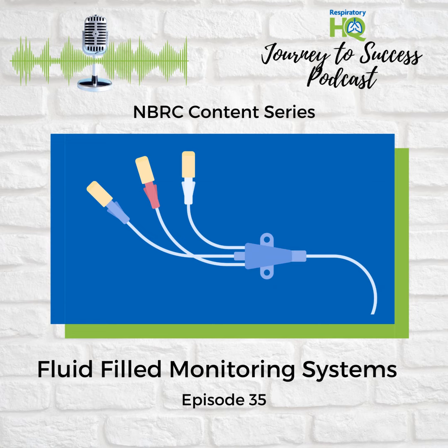And to understand those inaccuracies, we need to talk about natural frequency and damping. Okay, hit me with some physics. All right. Think of a guitar string. When you pluck it, it vibrates at a specific frequency, right? Right. That's its natural frequency. It's determined by the string's mass and tension. Similarly, the fluid in our monitoring system has a natural frequency, influenced by the length and stiffness of the tubing. So if the tubing is too long or too flexible, it's like having a loose guitar string. The vibrations won't be as precise.